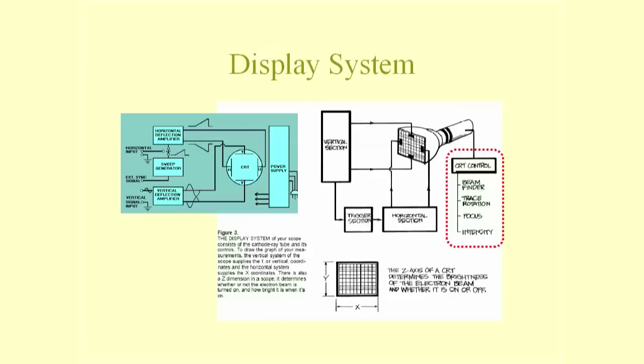Pretty simple. The display system itself has some controls, okay, that are separate from the other controls. Typically, you'll see things like focus and intensity. They're kind of self-explanatory. You change the focus of the beam that's going across the screen, and the intensity, how bright it is. There's also a trace rotation. On most of the scopes, you'll see it. It's usually a little set screw as opposed to a knob.